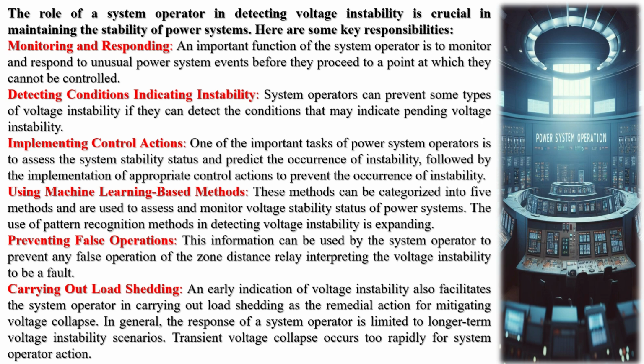Monitoring and responding. An important function of the system operator is to monitor and respond to unusual power system events before they proceed to a point at which they cannot be controlled. Detecting conditions indicating instability. System operators can prevent some types of voltage instability if they can detect the conditions that may indicate pending voltage instability. Implementing control actions. One of the important tasks of power system operators is to assess the system stability status and predict the occurrence of instability, followed by the implementation of appropriate control actions to prevent the occurrence of instability.